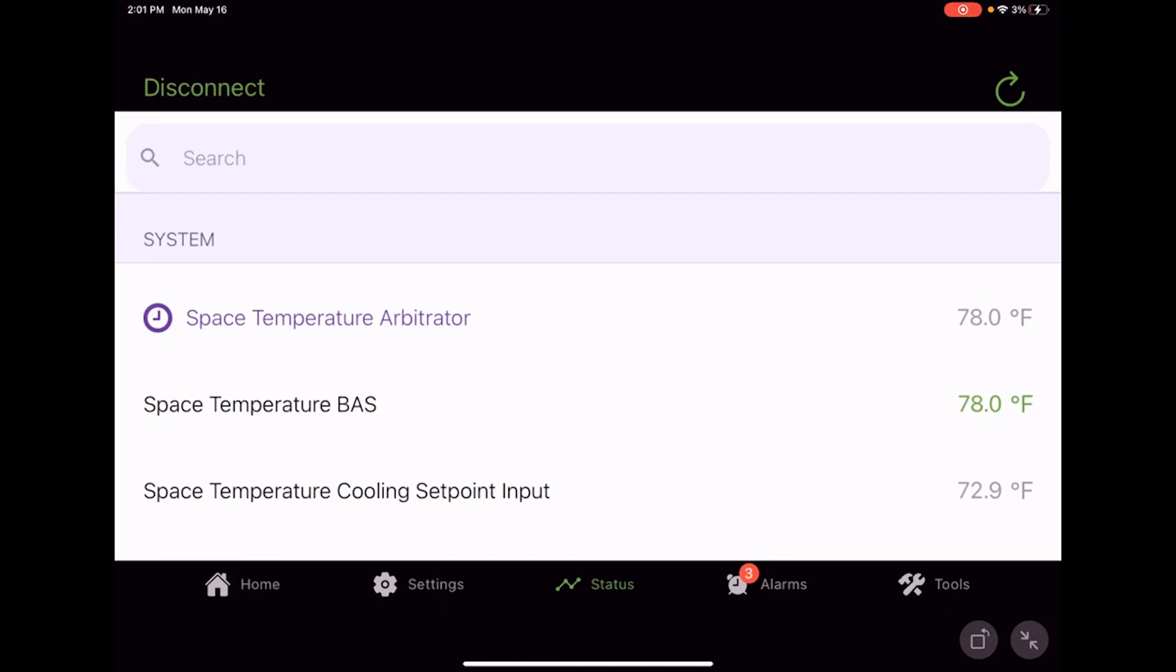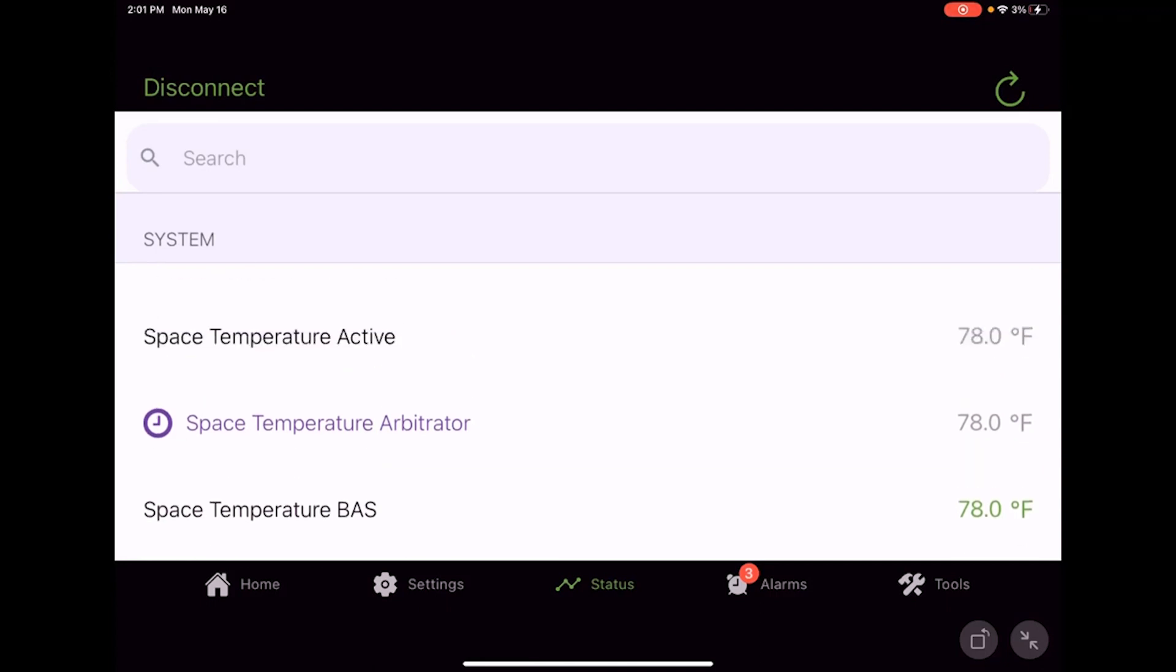If you recall back under the settings, I put the unit into BAS control, so when I change that BAS temperature now the unit thinks that space temperature is 78 degrees because we told it to use that BAS value.